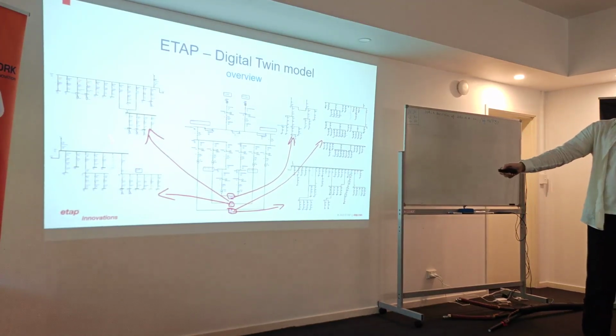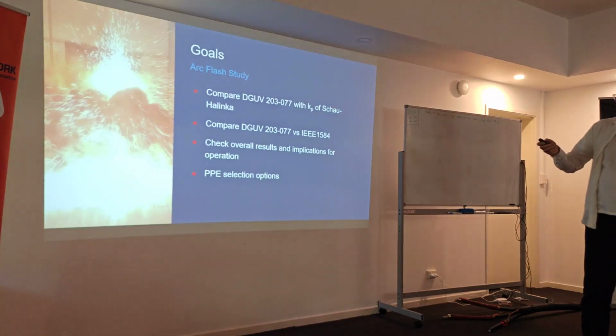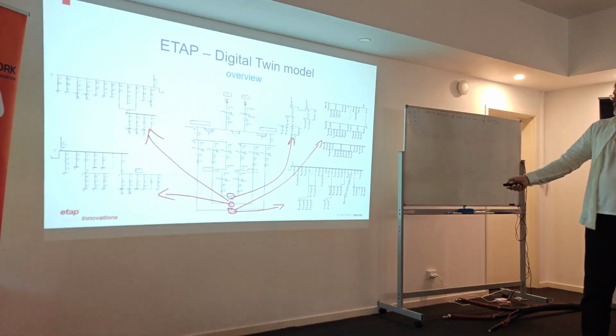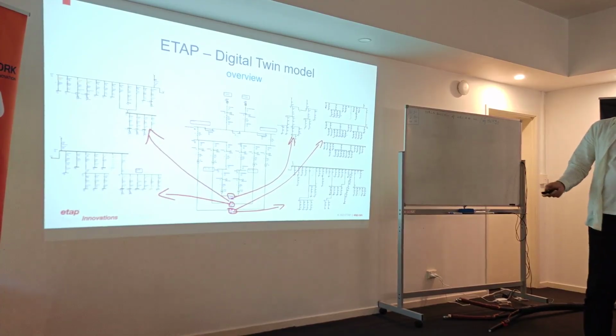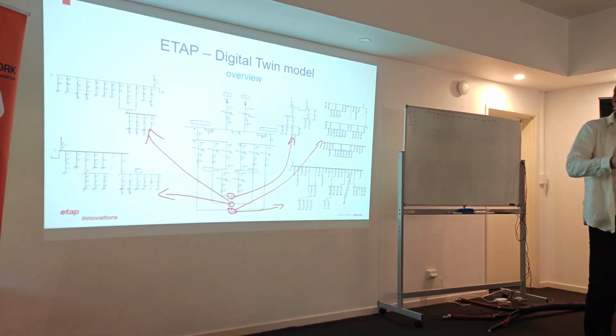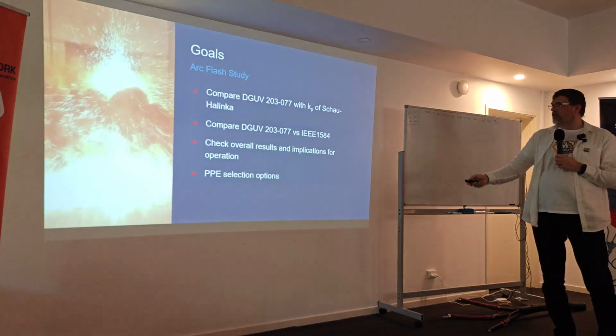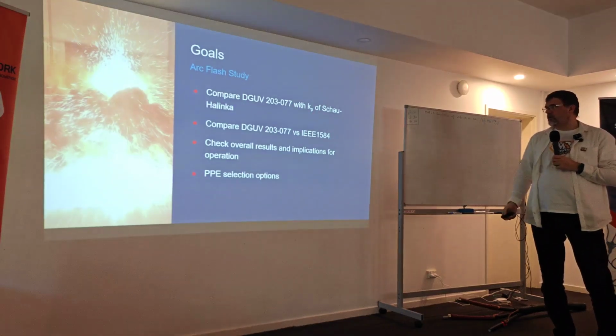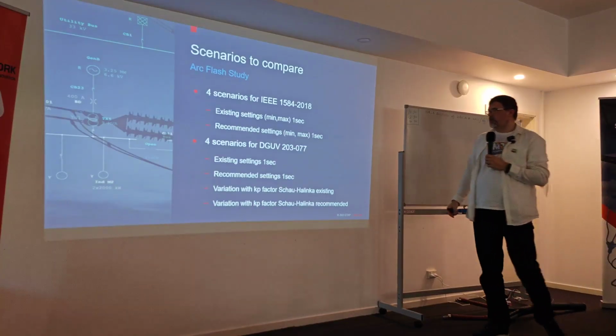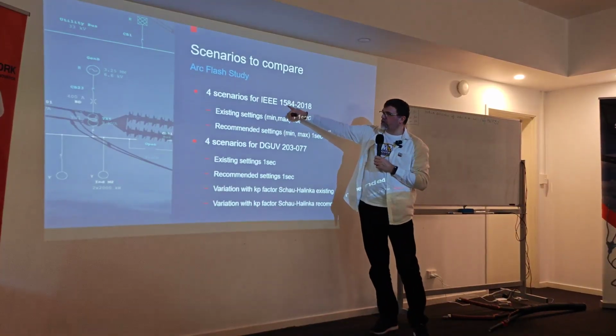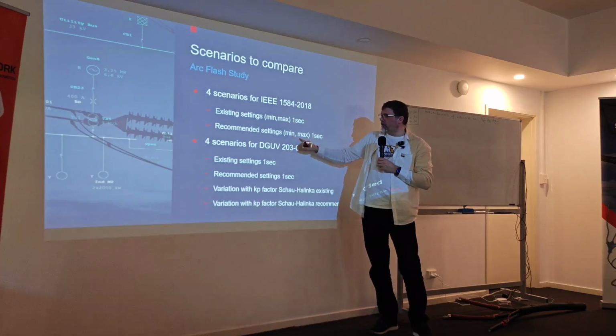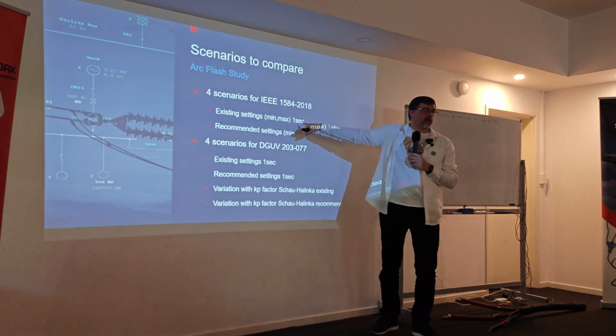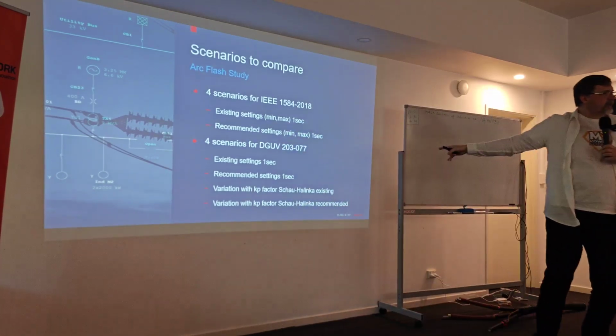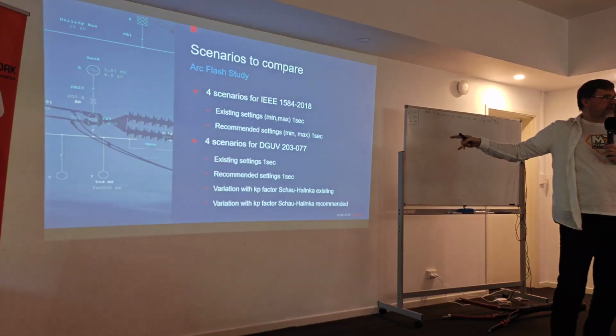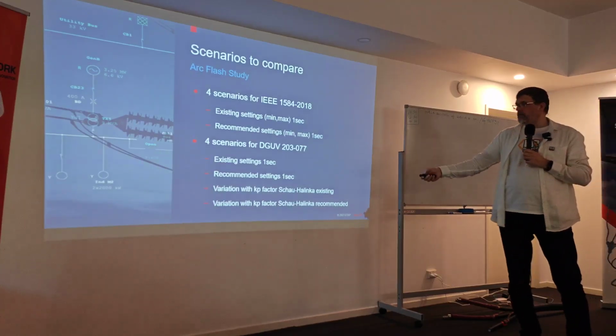So it's the same story. I took some of the existing project, because I calculated the complete project for this, with IEEE and with DGUV, but it's not about the comparison for you. I want to show you one thing, because I have a few things built in. That's why, again, software is useful. We have 4 scenarios, existing and recommended, so min-max, min-max, just to limit it. It's limited to 1 second, not 2 seconds, because DGUV has a limitation of 1 second as a tool, as an equation. So I limited it to compare properly.